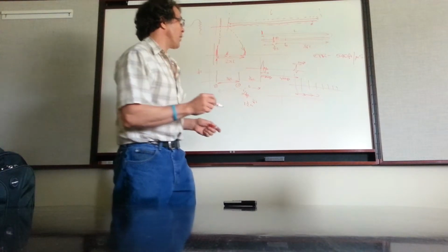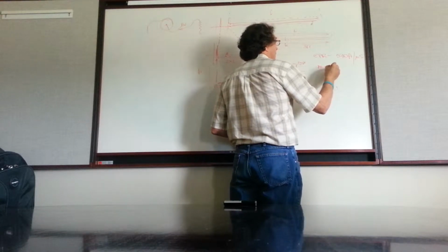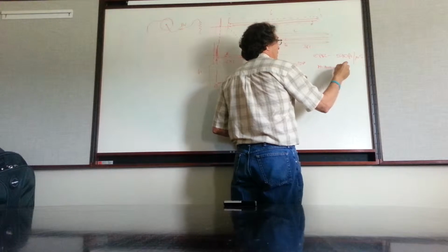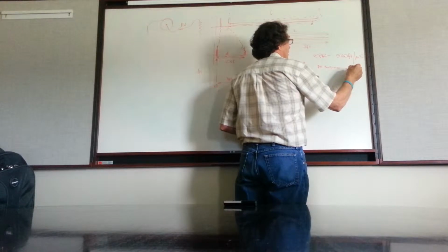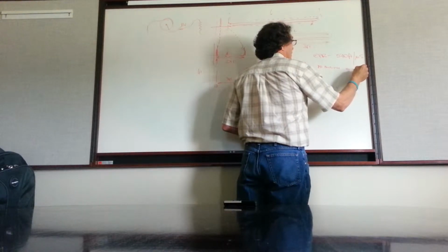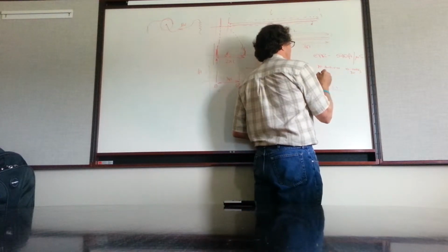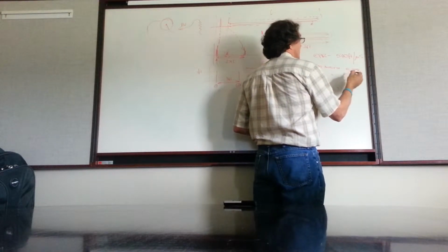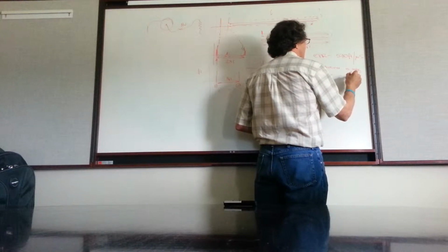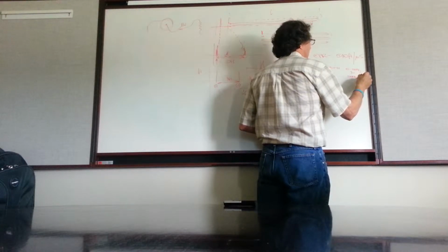Now, as we said, your two options are a PD amplifier, which is something like 10 to 500 kilohertz bandwidth. That's the standard amplifier. And then you have a PD site locating amp, PDSL, which I think is about 200 kilohertz up to 4 megahertz bandwidth.